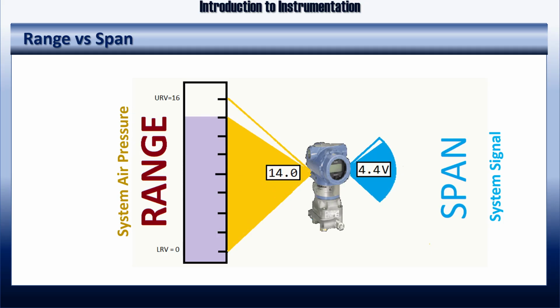Once we know we have that done, we can use that information and verify, as long as we have a way of visually seeing the process variable and a way of testing the current or voltage, whether it's calibrated properly or needs to be adjusted. We can also predict what the signal should be, or, if we have a signal, predict what the process variable would be. So we're going to go through those formulas in a little more detail, and you'll find it's basically what we did, but focusing on getting all of the information.